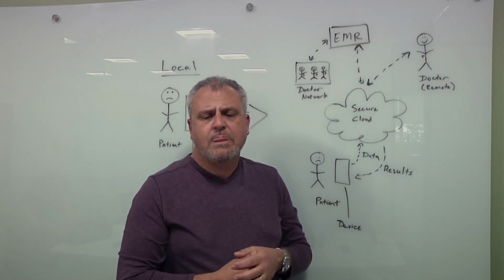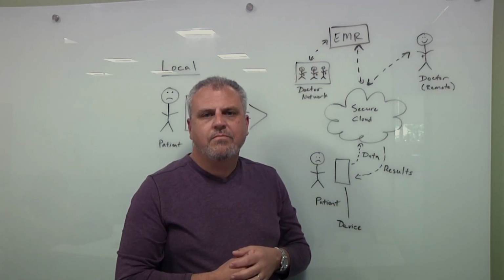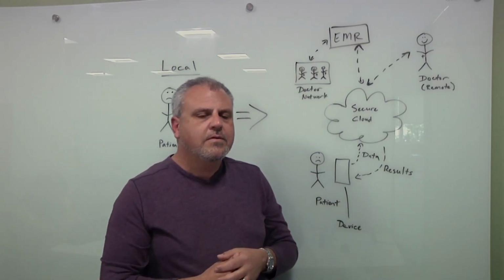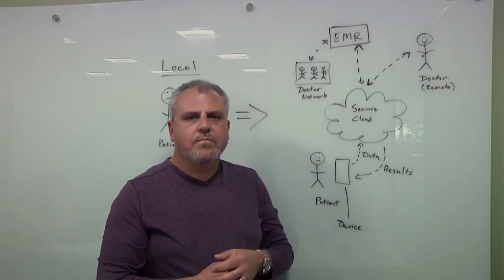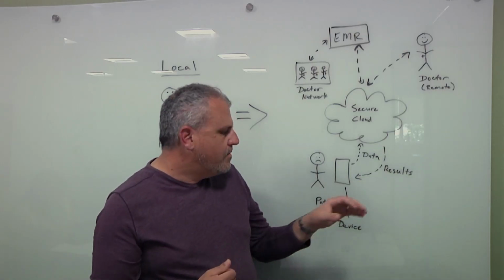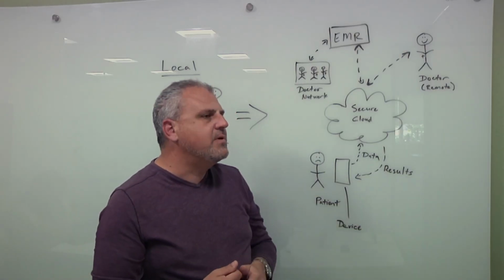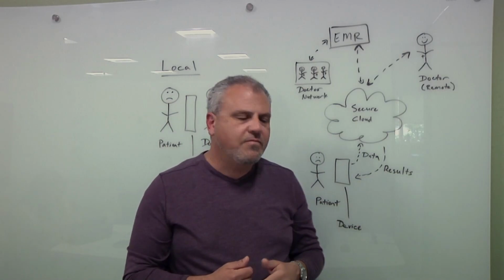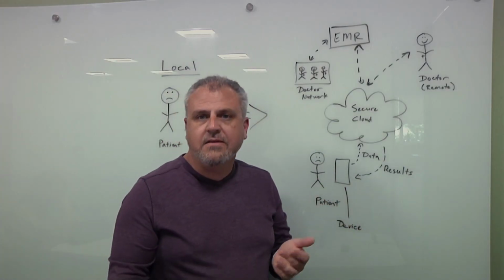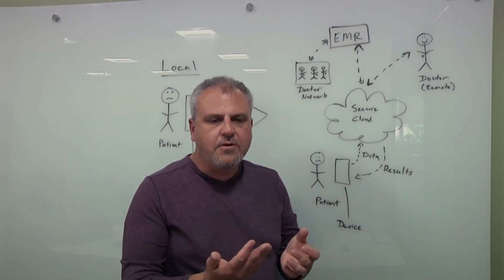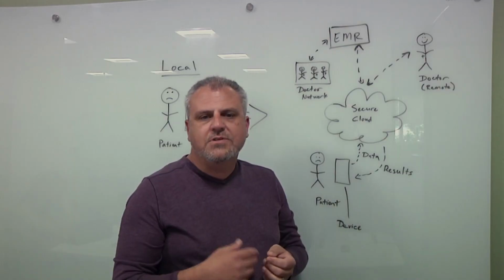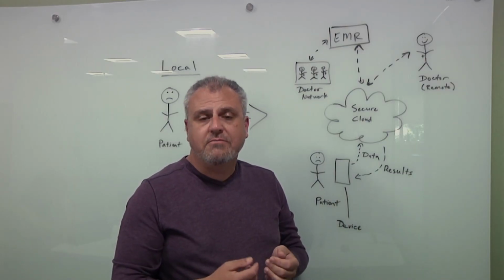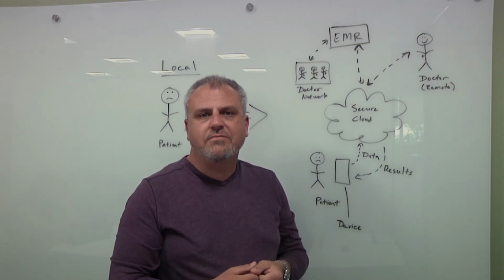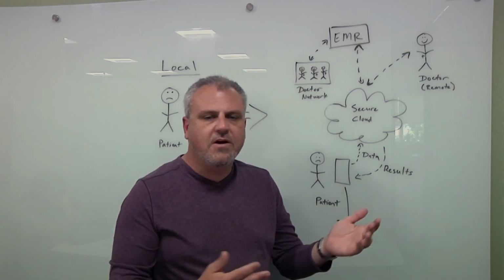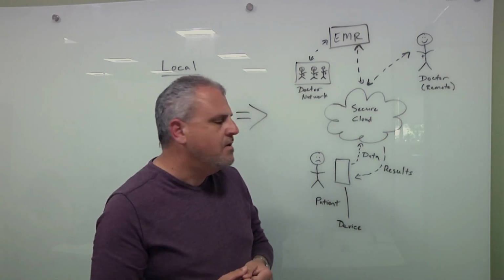And you've also got some constraints in terms of the standard materials that you have to use, right? Because there are rules about what you can put into the body or use for medical purposes. Correct. So, there's an incredible limitation on the materials that go into these devices. For something that contacts the skin or the patient in some other way directly, oftentimes there's a biocompatibility requirement, which restricts the number of materials that you can use so they don't cause some adverse reaction with the patient.